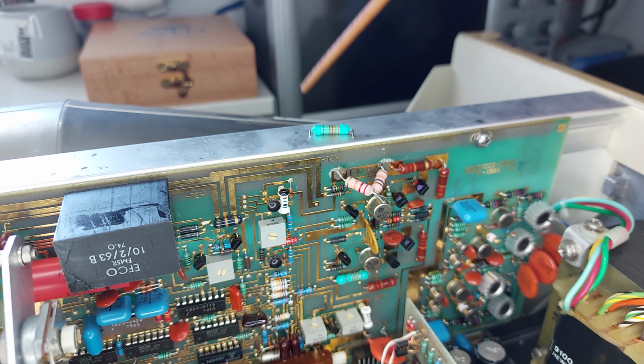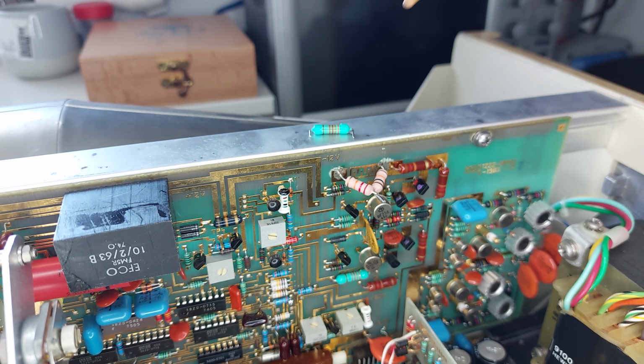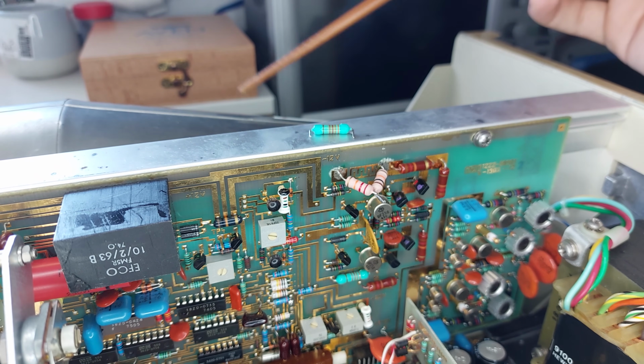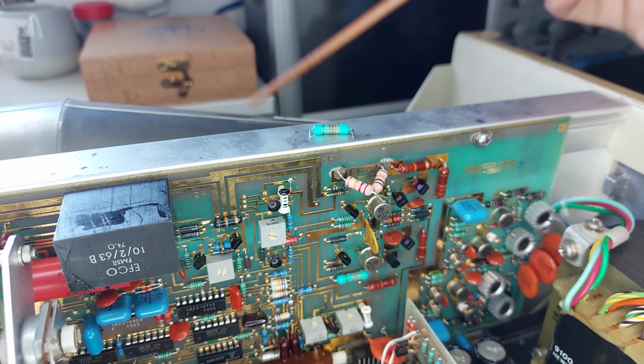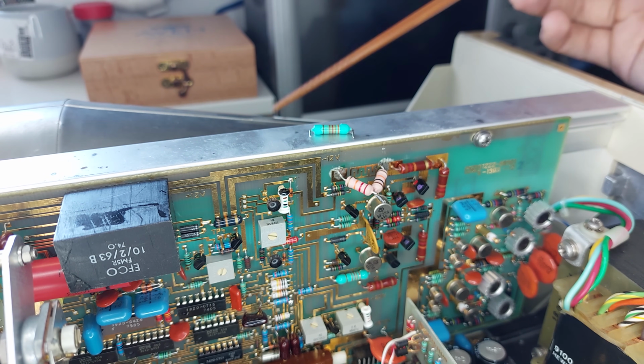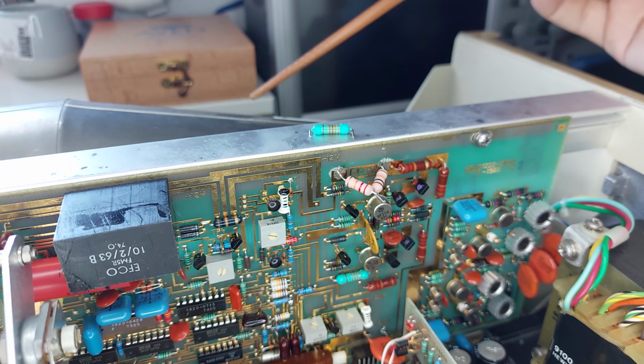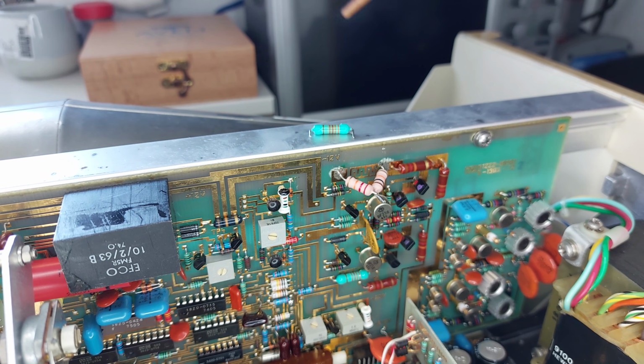Now, I don't think there's anything wrong with the B plus supply, and there's two reasons. The high voltage supply. The first reason is that all the functions of the oscilloscope that would be affected by a malfunction of the power supply for the high voltage are intact. The focus is intact, the astigmatism is intact, the beam is nice and sharp, everything works fine. However, that's not excluding a problem there.